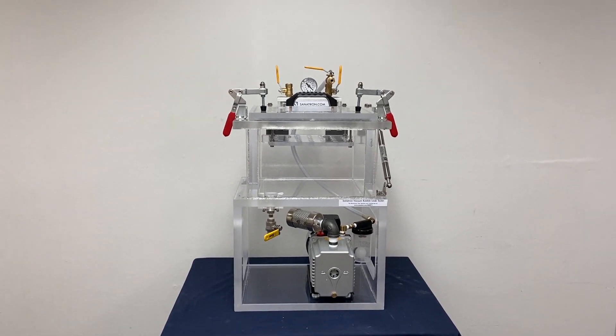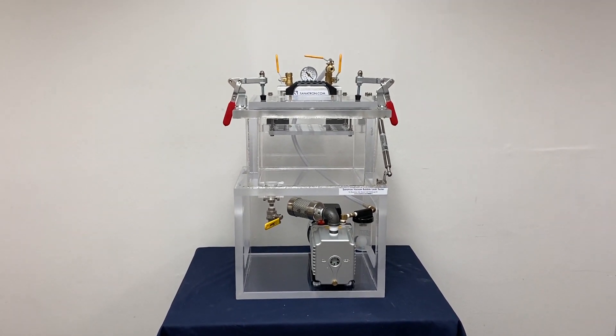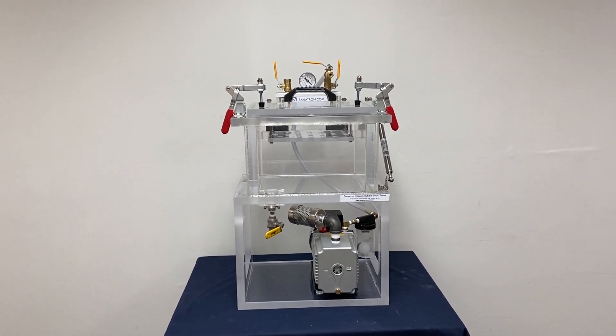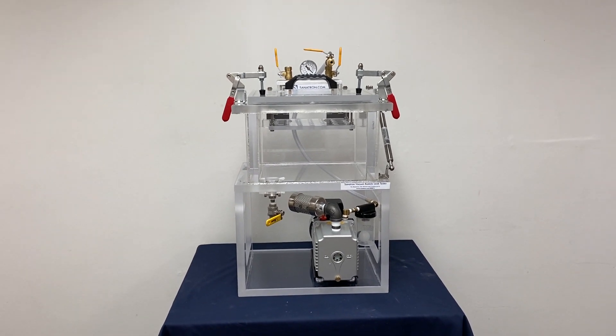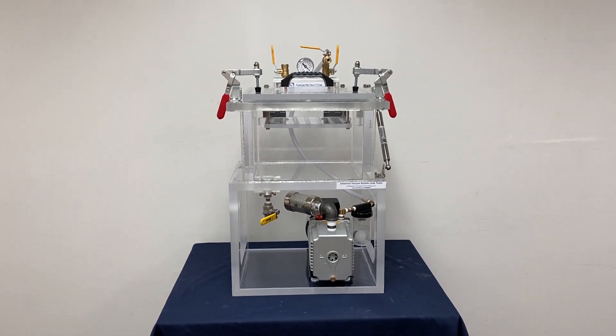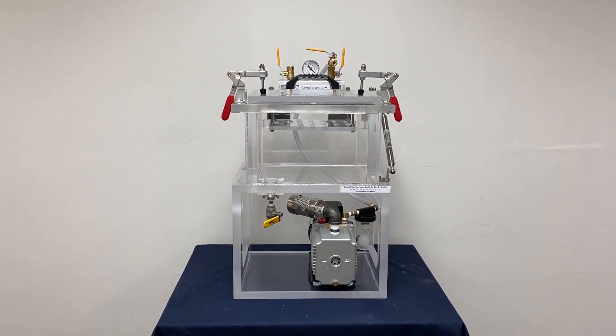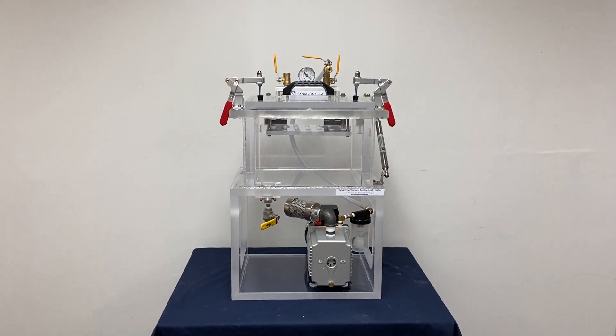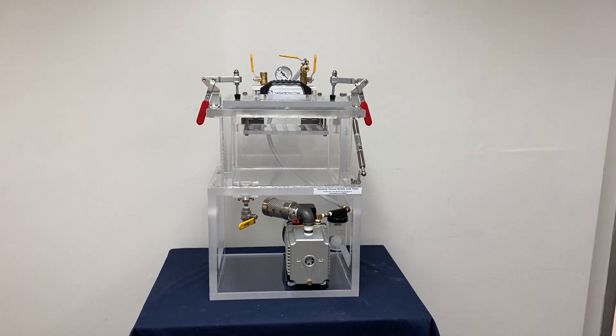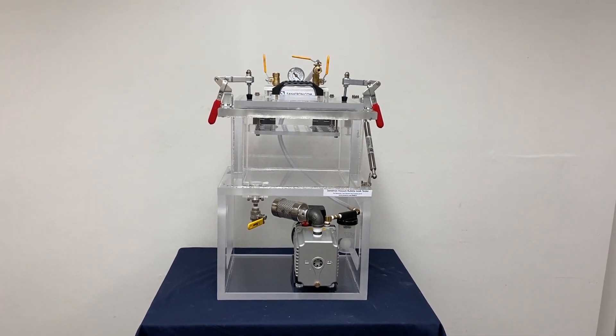This system is used to perform leak testing, quality testing, and heat seal integrity testing on pouches, stick packs, heat sealed trays, cartons, tetra packs, bottles - anything that's heat sealed or has air in it that can create a pressure differential and cause bubble emissions.